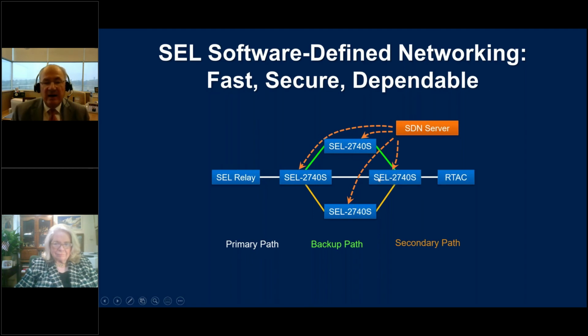For example, you can set the white line as the primary path, the green line as secondary, and the yellow one as tertiary—you program that here, and all the switches know it. Even if they lose control power, they come back on. When there are disturbances, the changeover time is rapid—sub-millisecond.